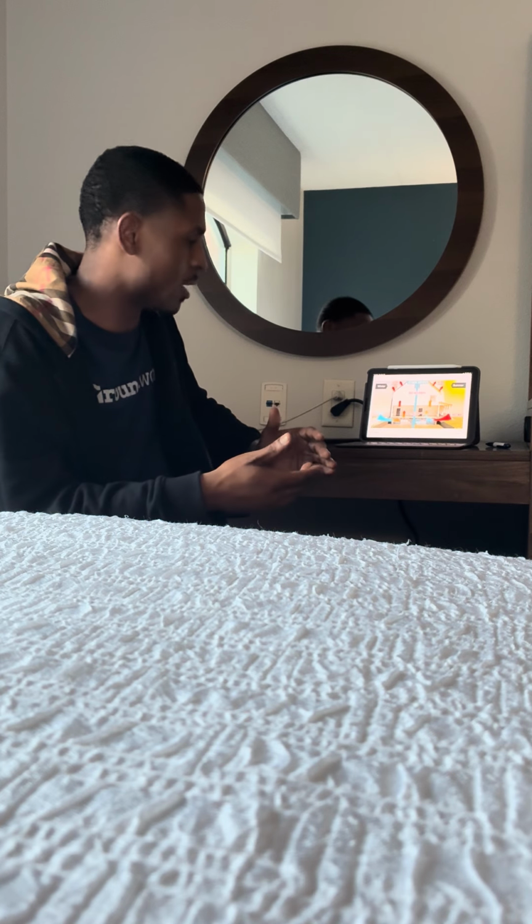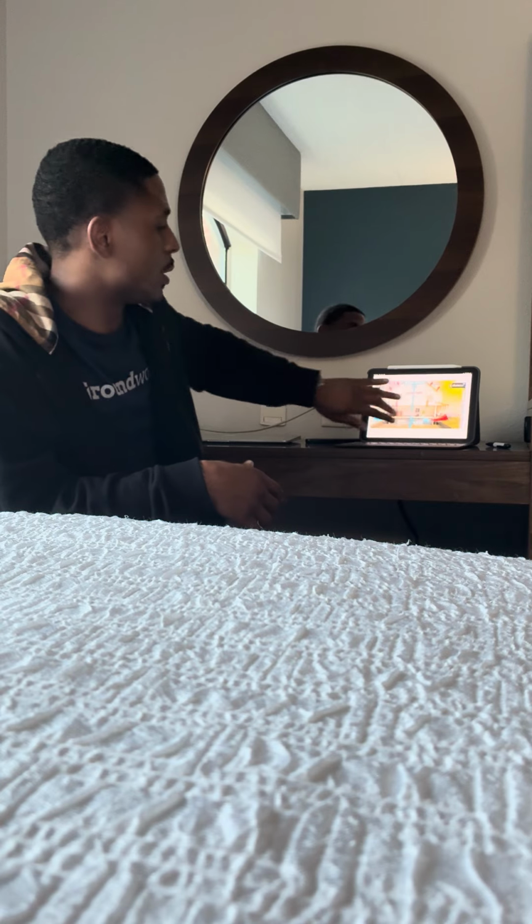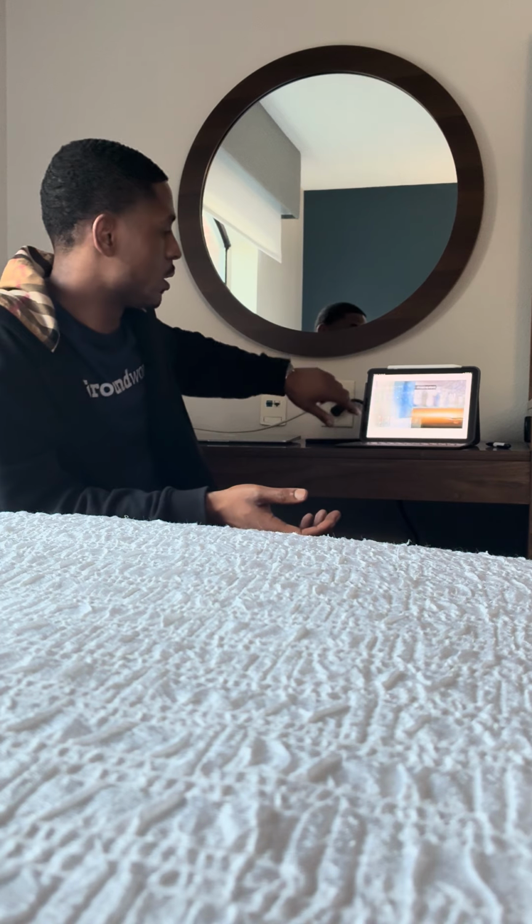And then in the summer, you're going to see that moisture start to come in through the hot air through your crawl space. And that's going to cause condensation on your duct system. That's going to lead to saturation of your insulation down there, as well as potential organic growth. Now, in the winter months, you will have those cold floors, and that's going to be a major sign that something's starting to go wrong.